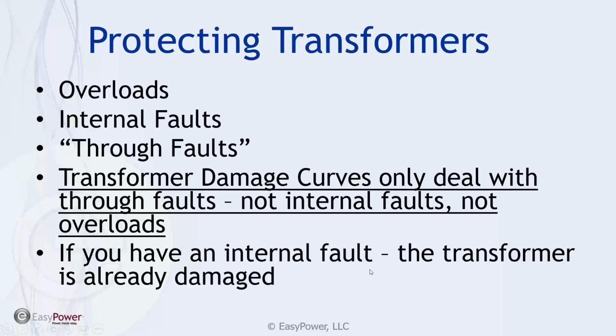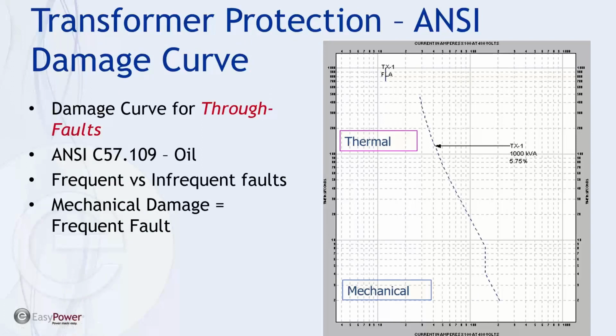So the typical display of a transformer protection, at least as defined by ANSI, is a through fault damage curve based upon the 100% probability that there will be damage to the transformer itself. So this is referred to as the damage curve. The upper area, actually the lower current but the longer time, is based upon the potential for thermal damage to the insulation and the windings. The lower part, which is the higher current section, if we look at the current on the bottom axis, is to prevent mechanical damage. This is because the high current through the windings can physically force the windings apart. And if that happens a number of times, there's a greater probability of mechanical damage to the transformer itself.